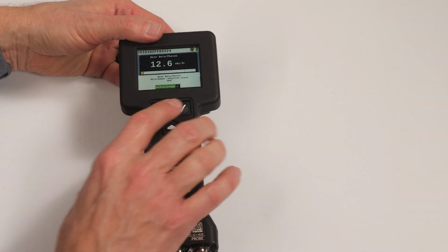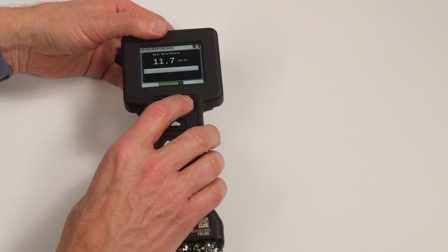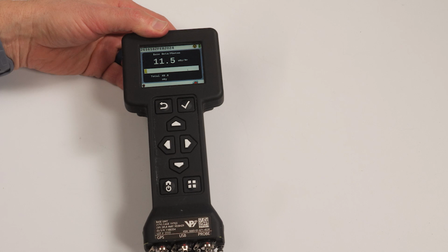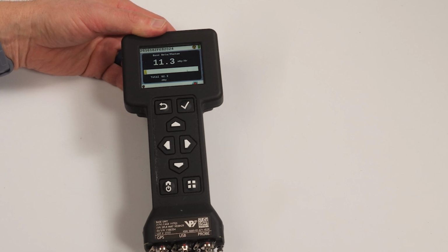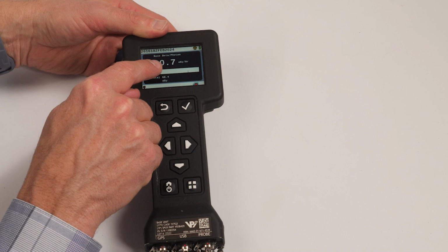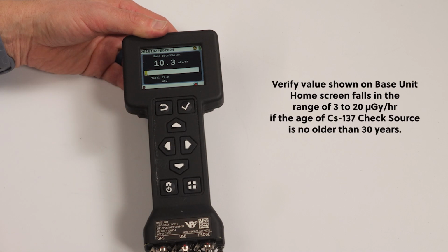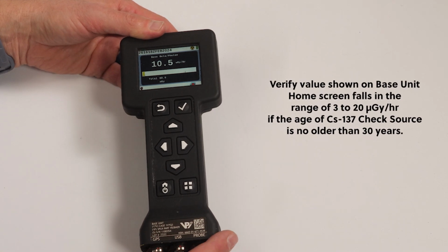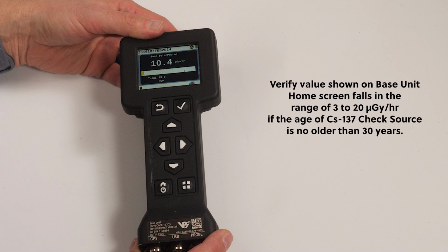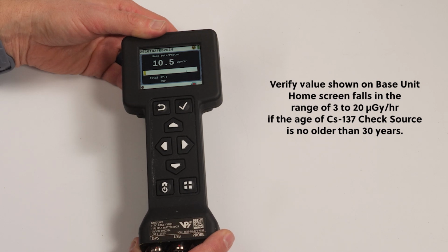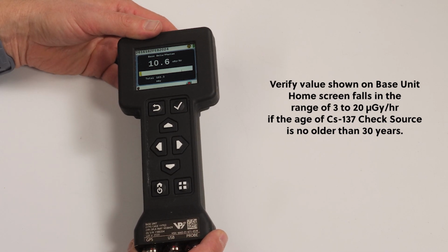If your alarm thresholds are set lower than the amount of radiation coming from the check source, the base unit will alarm. Acknowledge the alarm by pressing the Enter key as applicable. Hold the check source in place for at least 30 seconds, allowing the reading to settle. Verify the value shown on the base unit home screen falls within the range of 3 to 20 micrograys per hour. The check source must not be older than 30 years old.